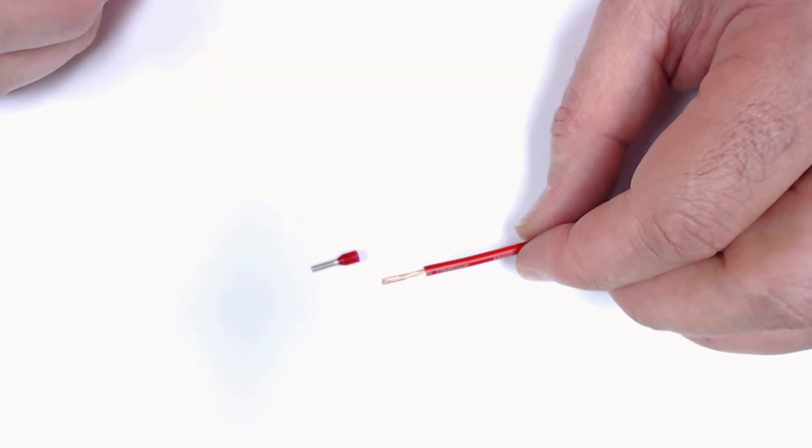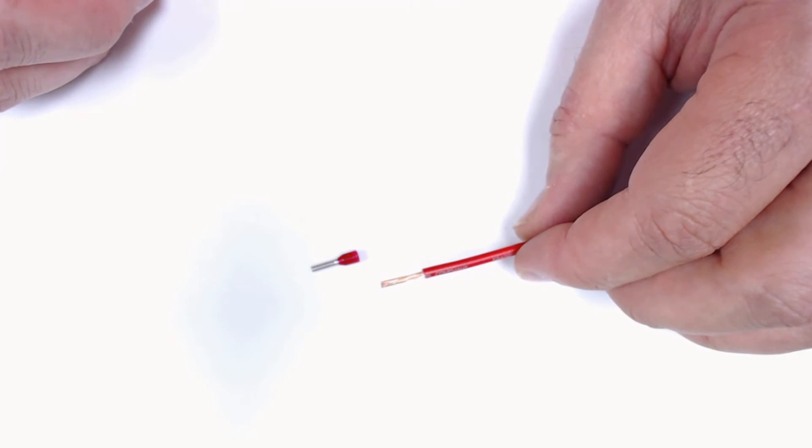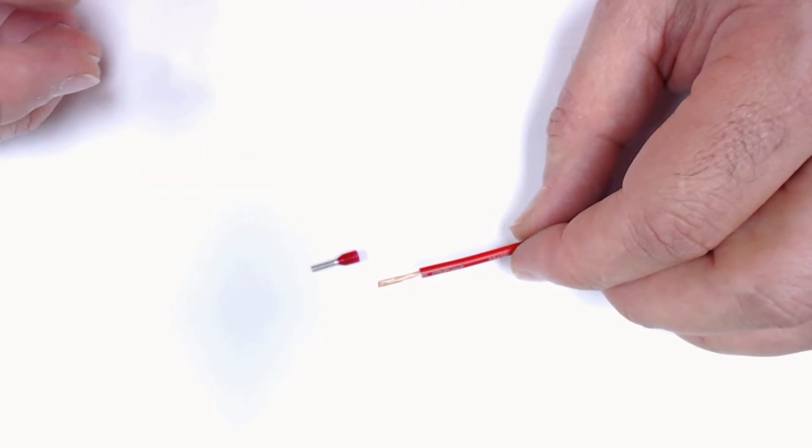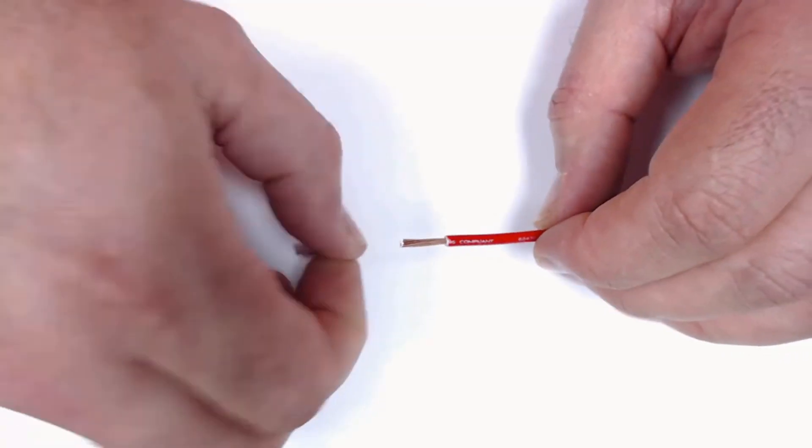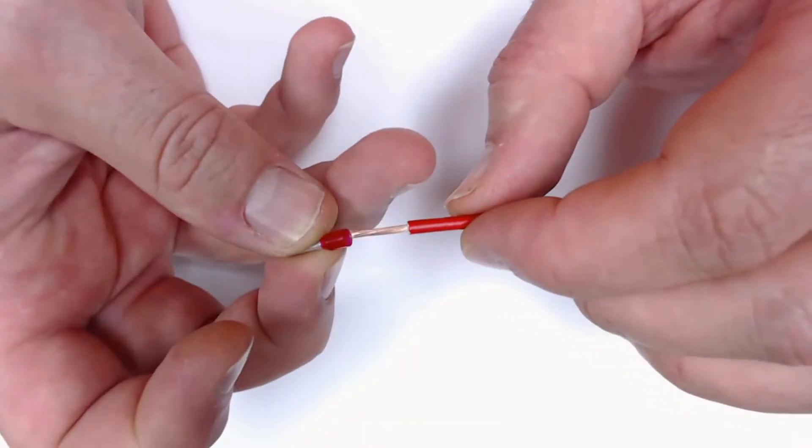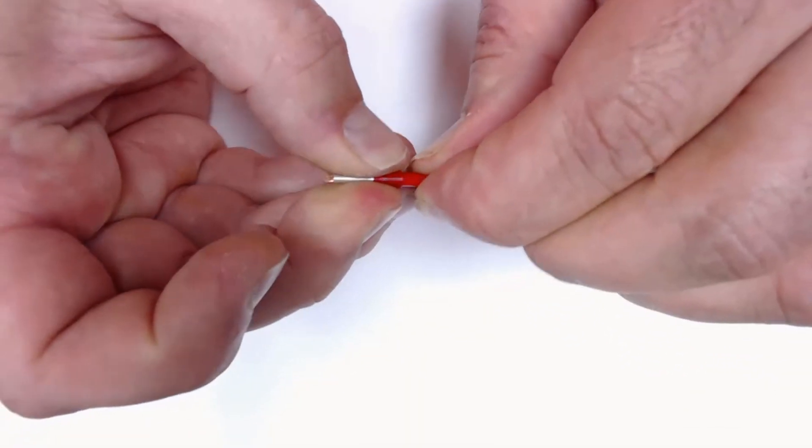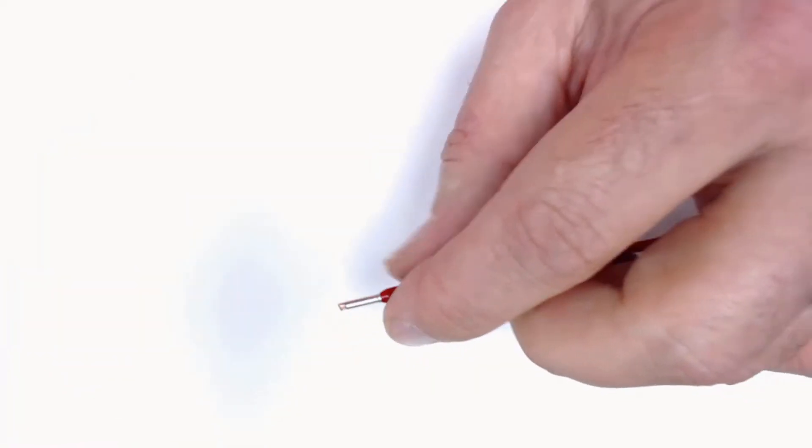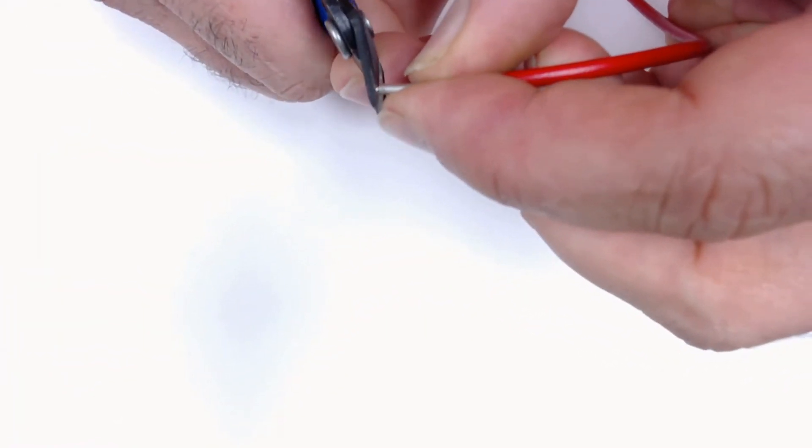Here we have one of our 16-gauge ferrules that I'm going to crimp on here and show you a little trick that I learned to help the ferrule insert into the Weidmuller connector a little easier than normal. We're going to do the same thing we did in the previous demo. We're going to make sure the strip length is right. Now it sticks out a little bit past here, so we're going to trim that flush. We don't want those strands sticking out too far.